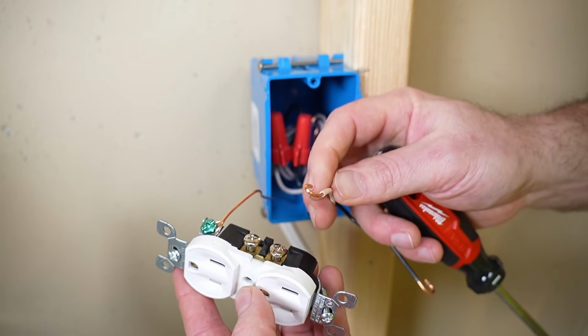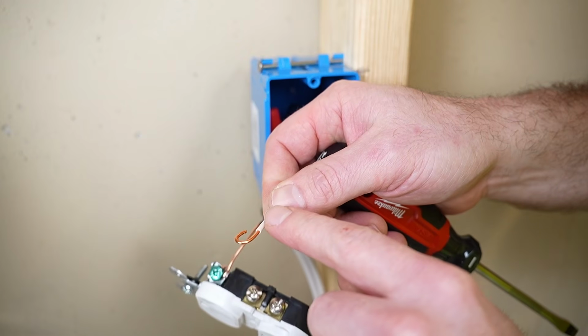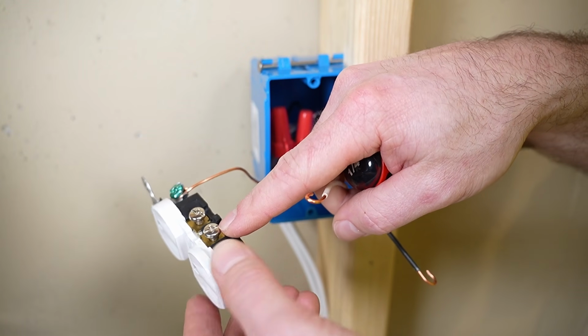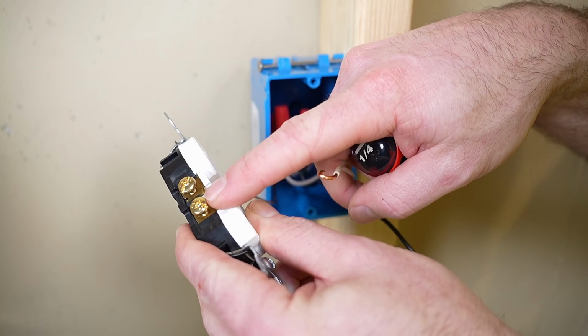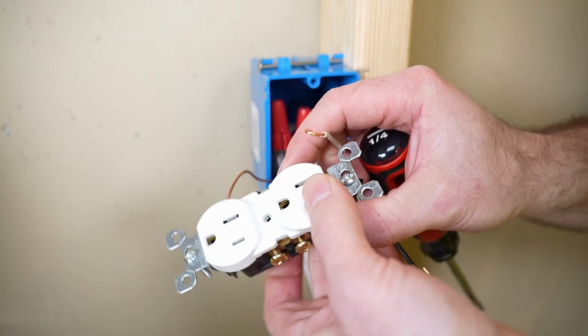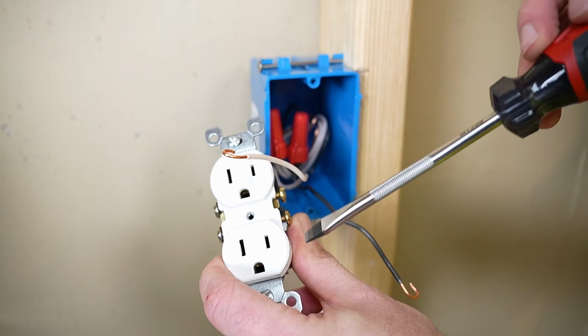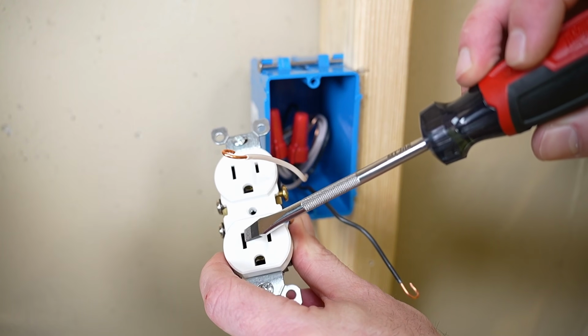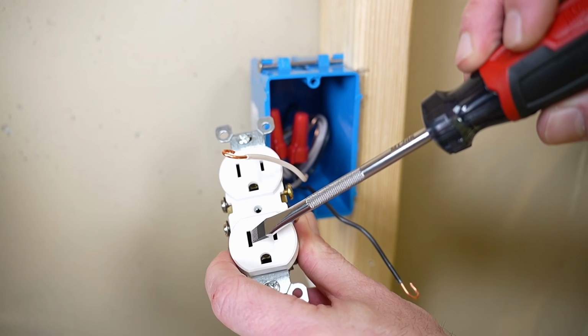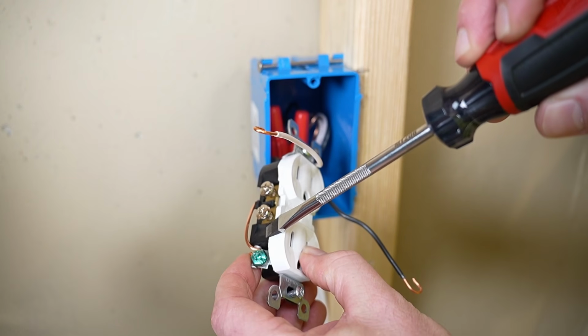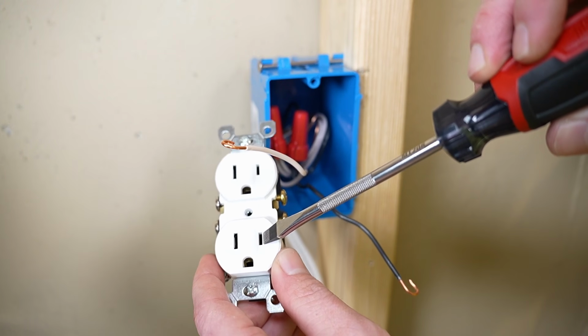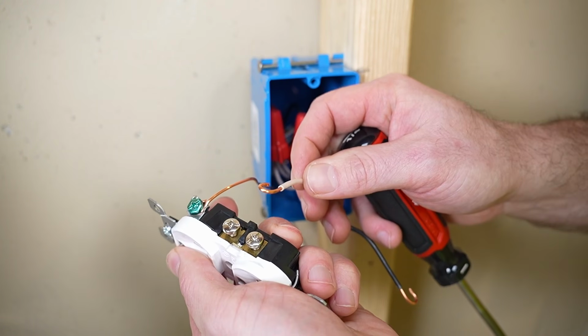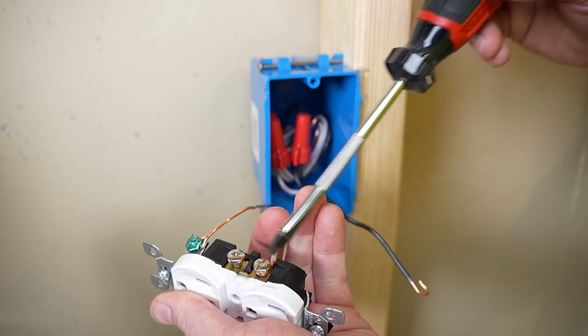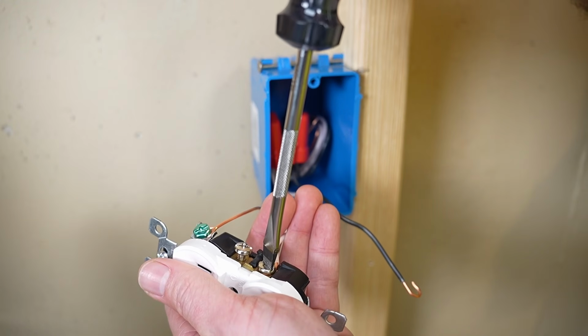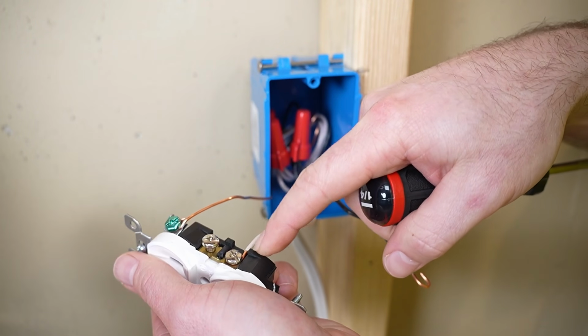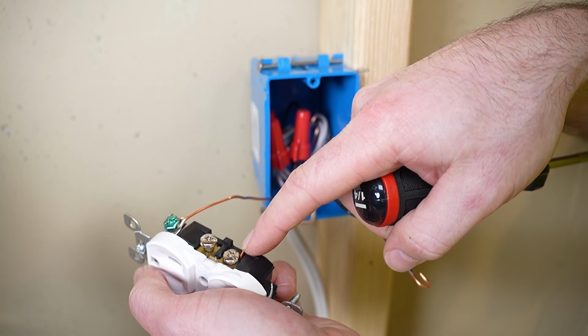Now we'll go ahead and do the same with the neutral. The neutral wire gets landed on the silver colored terminals. The brass or gold colored terminals are the hot. Another way of looking at it is on a receptacle, the larger of the eyes, if you will, on the face that's a receptacle, the larger eye is the neutral, and the one that's winking at you is the hot. So on the silver screw, we're gonna put our neutral. You could choose either one, it doesn't matter. And snug it down. Again, making sure that the wire is looping the same direction that the screw is tightening.